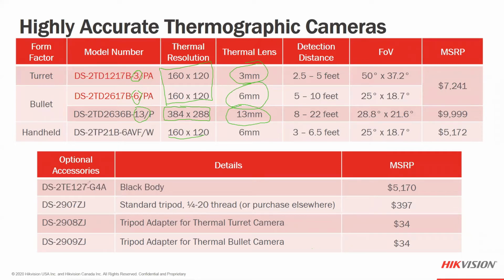For optional accessories, we have the part number for our black body calibration device. You can see that adds a lot of cost, but it does increase the accuracy level. It also increases installation time and other factors, since the black body has to be mounted within the field of view of the camera at all times.